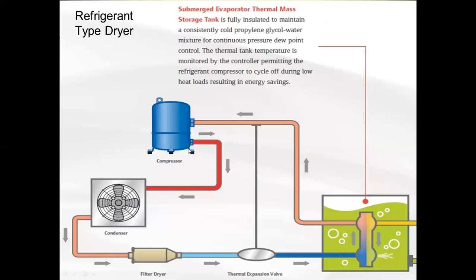So this is the refrigeration side, and this is just a typical refrigeration device. We have a compressor. The gas comes in on this side, and then we compress it so it's hot superheat through here, and goes down to a condenser. This is the high pressure side of the compressor down here, so this is superheated vapor. We cool it down in the condenser, condense it to a hot saturated liquid, filter dryer.